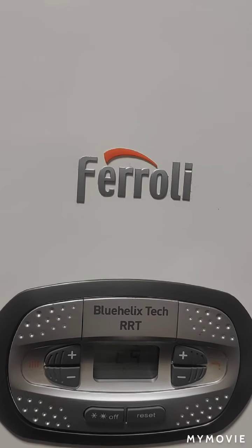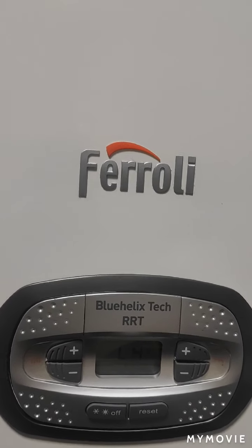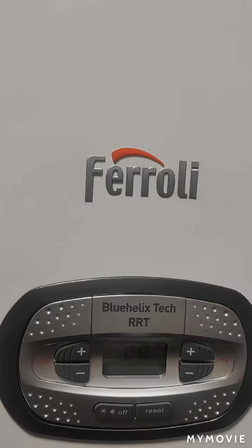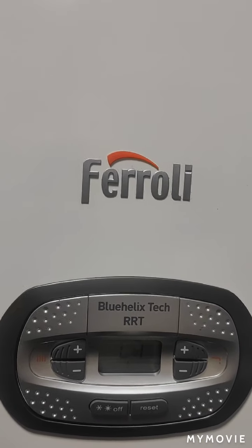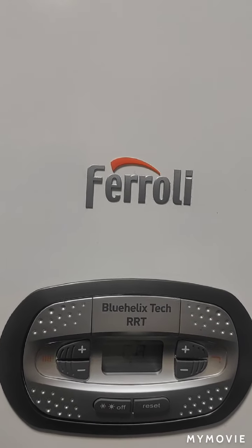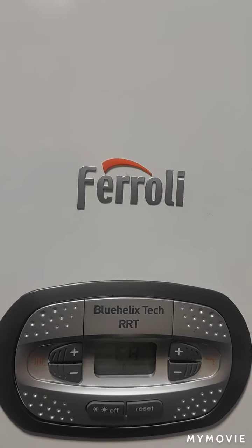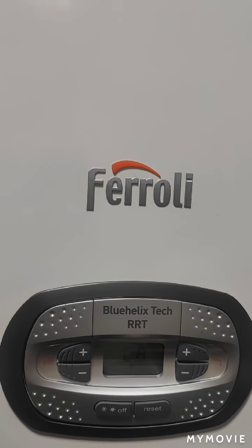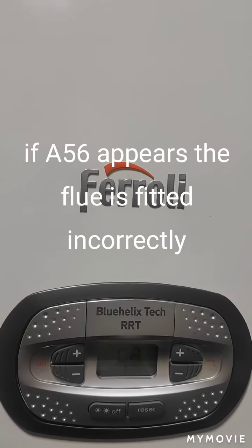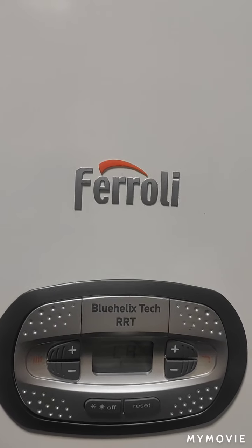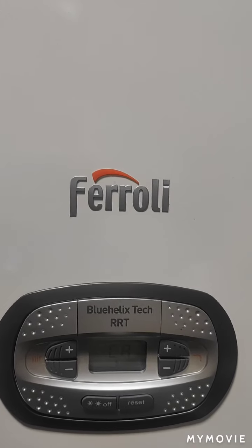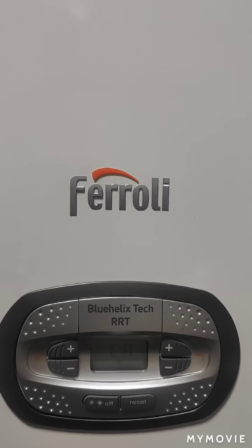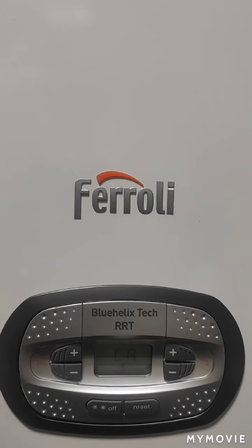So that's how you do the calibration if you've changed a gas valve or you've had to change a circuit board, and it will take about a minute. So what happens after it's done its calibration, you'll just go back to the same screen as normal. Just to note, you don't have to do this every time you do a service. It will do it automatically on its own.